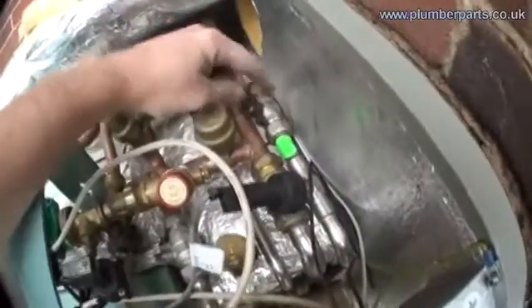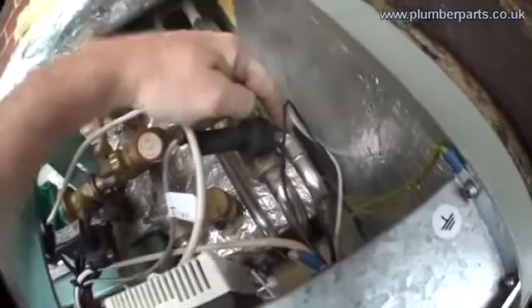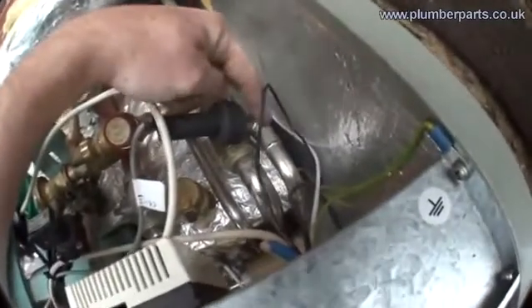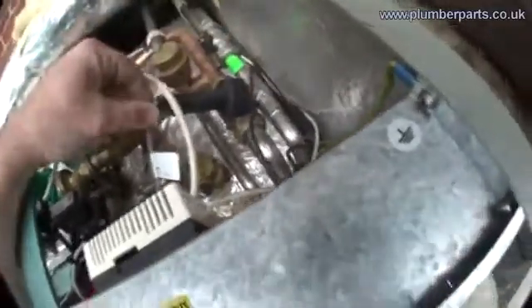I just wanted to show you the two different routes that the two bodies of water take. You have your cold water that comes in here, goes through an isolating valve so we can switch it on and off. Now this is the flow switch here. All that is is a small paddle — imagine your light switch, but instead of your finger pushing the light switch, it's the flow of water going over a small paddle. So the paddle clicks and turns the boiler on.